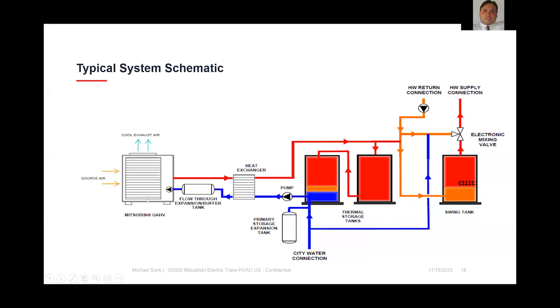But even though this heat pump has basically a double wall heat exchanger, and typically they do, in the event of failure or corrosion of one of the sides of that heat transfer, whether it's the refrigerant side or water side, there's still concerns with regard to water quality and contamination. And because you're dealing with such high pressure refrigerants and wanting to minimize service work that may be required through the life of the building on that outdoor unit, most manufacturers, including Mitsubishi, are choosing to separate the potable side of the system from the actual heat transfer that's occurring directly through that outdoor heat exchanger. And so that's typically done with a brazed plate heat exchanger that's potable rated, located indoors.